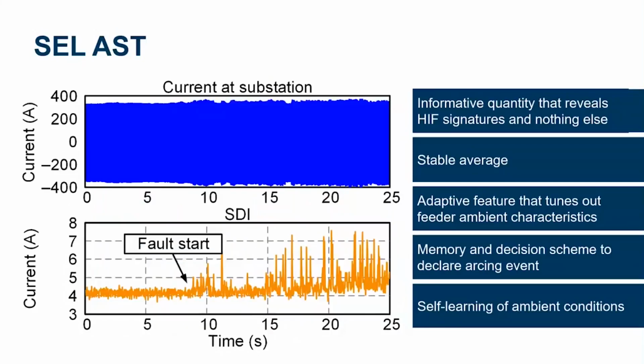Now, if we look back, this is once again from another down conductor test. So let's look at this case. If I'm just looking at my measured current at the substation, you can see something might be going on here, but it's very difficult to say that this is a high impedance fault or really anything, just looking at this current alone. And for sure, our traditional ground fault protection is not going to be able to pick out this fault, especially on a 4-wire multi-grounded system, because we're not going to be sensitive enough to detect it.